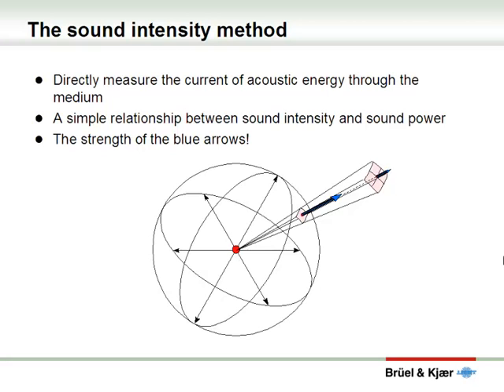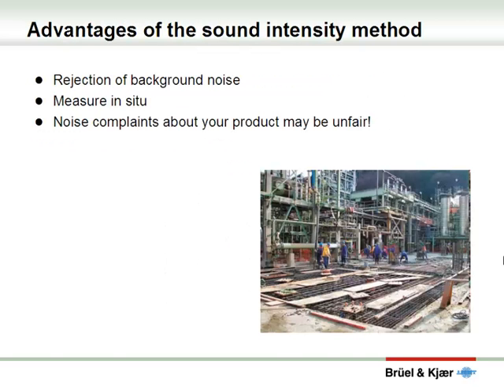The sound intensity method directly measures the current of acoustic energy through the medium, and there is a simple mathematical relationship between the sound intensity and the sound power that we need. Sound intensity, if you look at this picture, is really the strength of the blue arrows. The sound intensity method will help you to reject the influence of background noise and enable you to determine sound power of a source in situ at its actual location. If your product is one of the machines on this installation and there is a noise complaint, the sound intensity method will help you to reduce the influence of background noise of other sources.